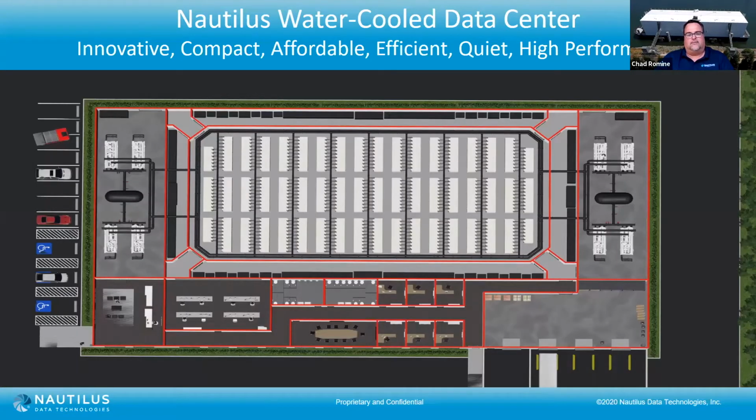This is a view inside the data center. On either side of the data center hall, you'll see our cooling distribution units. That's the open loop and the closed loop coming together, and that's where we do the heat transfer, the heat exchange. Then we move the water into the closed loop system of our data centers. Because we're capturing the heat at its earliest exit point, we have no space between our racks. Regardless of whether somebody is running a 10 kW rack next to a 40 kW rack, we are perfectly fine with that. So we're able to improve the rack count within a given floor footprint. You go to the next slide.